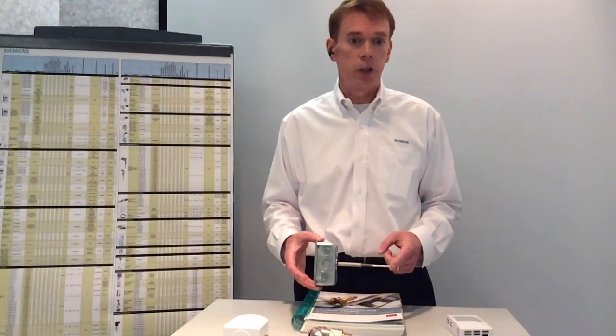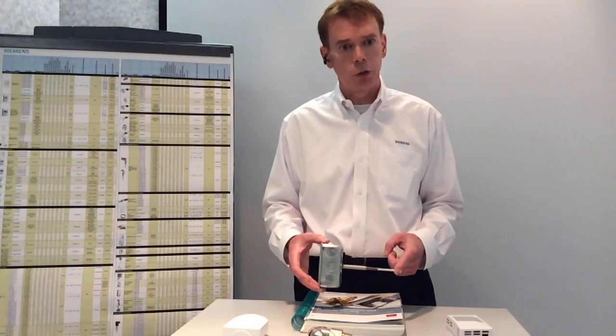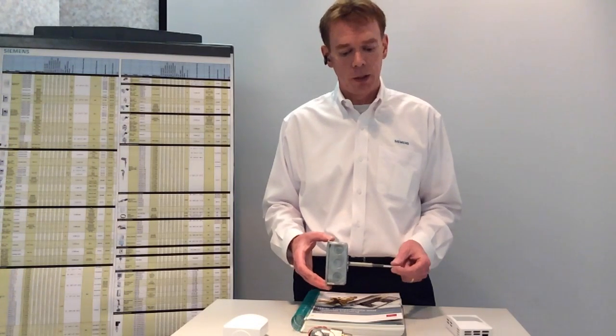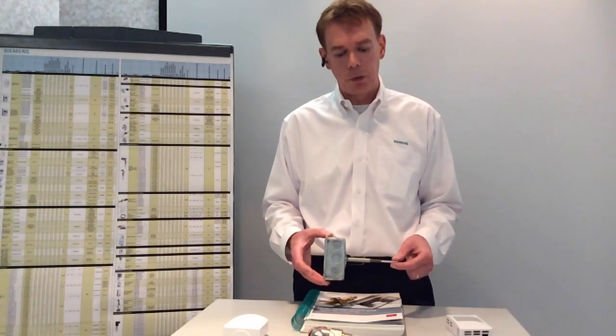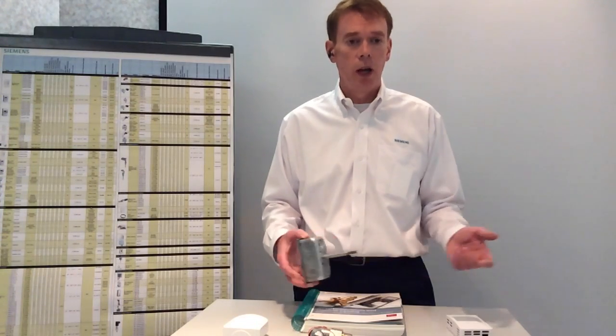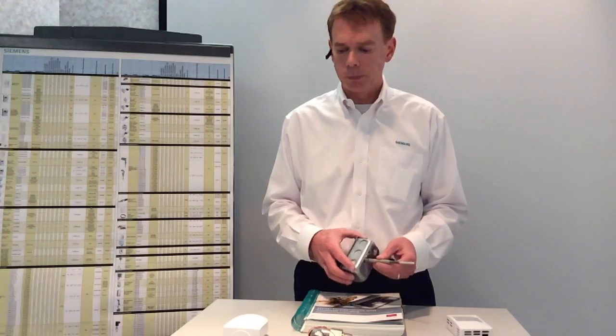Typically, when you get above 2 feet on the insertion for the duct temperature sensors, we go with a flexible sensing element rather than a rigid sensing element like you see here, and that's to make installation a little bit easier.